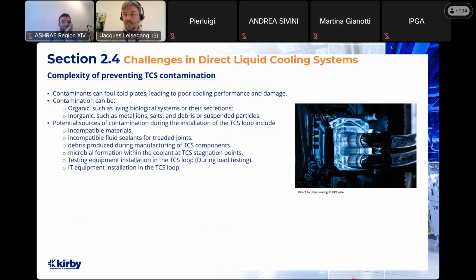The next challenge we have is the complexity of preventing contamination in your TCS. Contaminants can foul cold plates, leading to poor cooling performance and damage. This again, we're talking about the direct coupling of the liquid-cooled system. You're very much tied into the warranties of all this IT equipment. This IT equipment can be eye-wateringly expensive, and if, as a result of an improper coolant or coolant chemistry, that damages the cold plates and overheats the servers, there is a massive repercussion for us as a result of that.